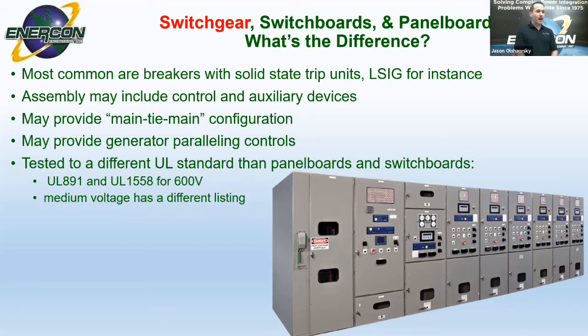And so assembly may include control and auxiliary devices, may provide some type of a main tie main configuration. There are several different configurations that you could use just based on spec requirements and what the site needs there at the facility. And there may also be generator paralleling controls. So for standby operations, you would have controls there for bringing up a generator in case you lose utility.